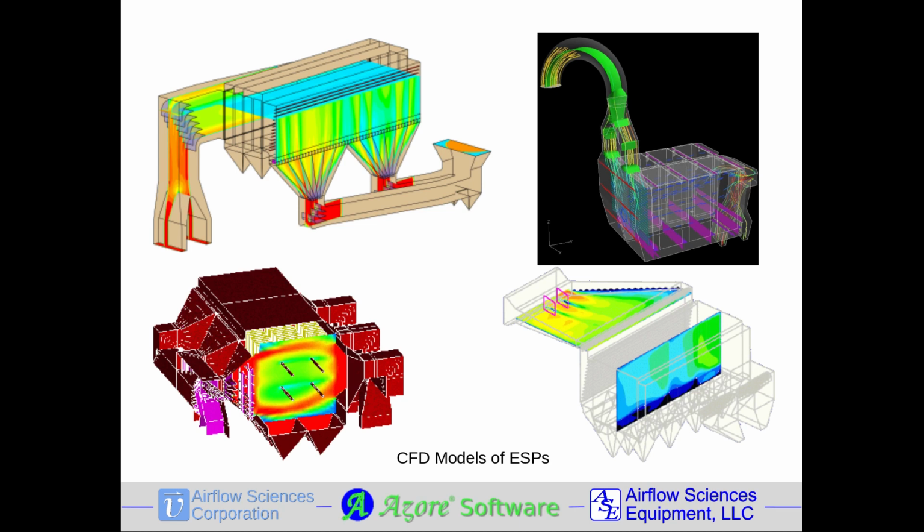a stack. Incorrect design, on the other hand, can lead to problems such as lost product, the use of more or larger fans, or particulate buildup in locations that can threaten the structural integrity of supporting ductwork. Flow modeling and field testing are effective ways to ensure optimum ESP design and performance. Modeling is often done during the initial design phase, but both modeling and testing can be performed on an existing ESP.